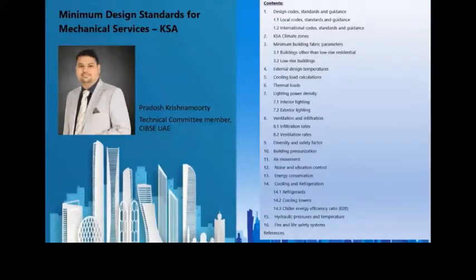Coming to the KSA climate zones, unlike UAE, KSA is a vast area and is predominantly distributed in 3 different climatic zones. The guidelines provide where each region falls, and there is a map which shows, depending on your project location, which climatic zone to be chosen. In addition to that, there's also guidance on what should be the external design temperature conditions to be considered depending on your project zone. While the SBC code particularly refers to the usage of 1% design conditions, the guidelines recommend to use 0.4 conditions predominantly to maximize the thermal comfort in case of temperatures falling outside that 1% region.